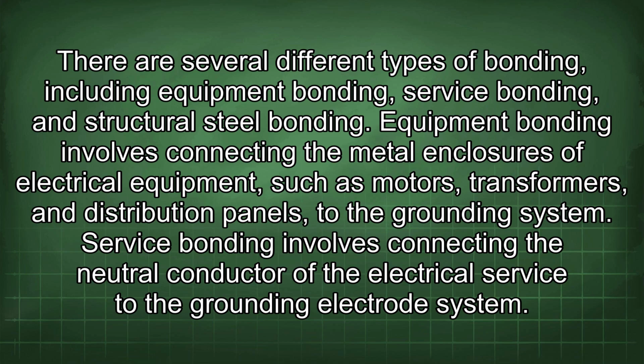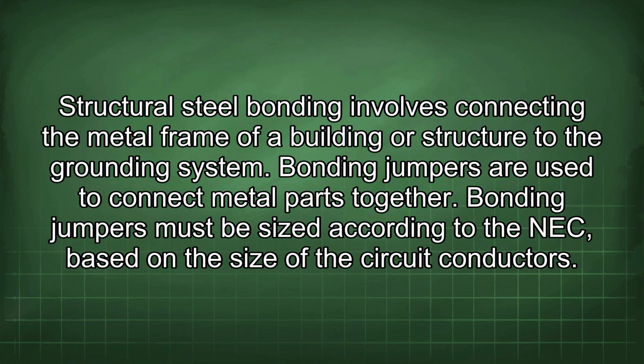Equipment bonding involves connecting the metal enclosures of electrical equipment, such as motors, transformers, and distribution panels, to the grounding system. Service bonding involves connecting the neutral conductor of the electrical service to the grounding electrode system. Structural steel bonding involves connecting the metal frame of a building or structure to the grounding system.